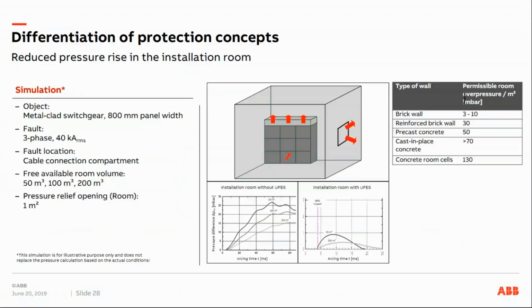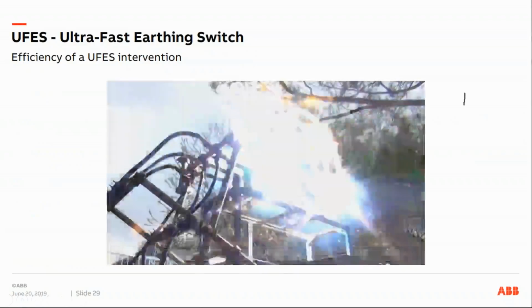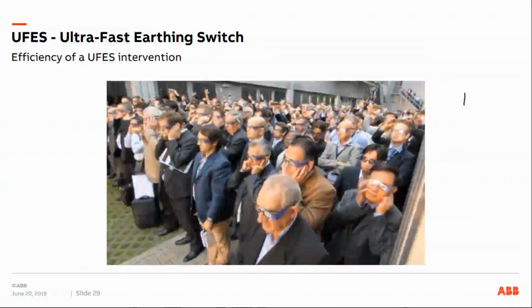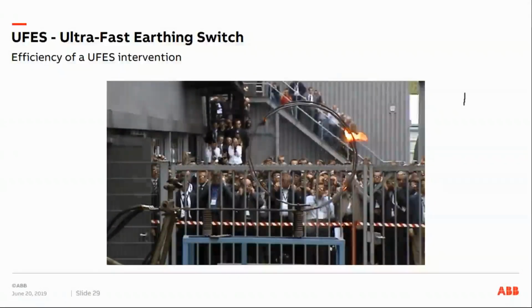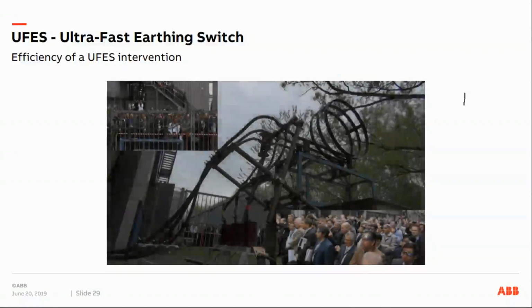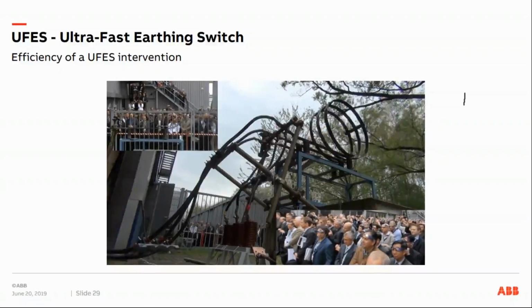Here on this slide, I wanted to show you again how the pressure is rising in a switchgear room where you have the UFES or where you don't have the UFES. As you can see, with the UFES, it's way below compared to the installation room without the UFES. So here's again a video for you. Let's see what happens if we have a UFES installation. Here again, we see the arc fault without the UFES, which you saw in the beginning. And now let's pay attention to the primary switching elements on the bottom.